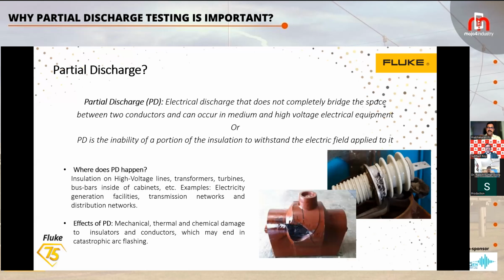Where can it happen? Any insulation, any high voltage lines, high voltage transformers or turbines or bus bars or cubicles of bus bars and switchgears, or even the high voltage cables or their joints. All the places wherever high voltage is present, you can expect partial discharge. What can it do to the materials or the equipment? It can have mechanical effects, or thermal effects, or chemical damage to the components, and it can also have various other unwanted effects. We will see those things in the later slides.